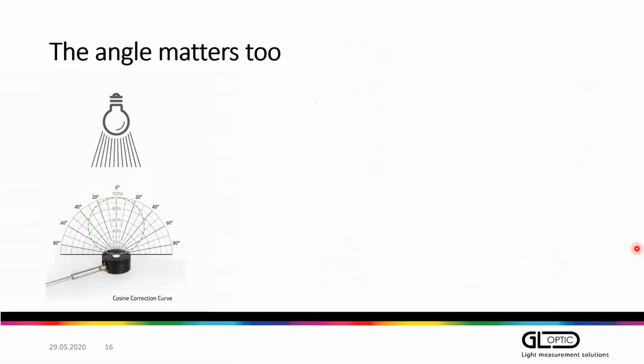What about the angles? The same thing. If you change the angle, then the amount of energy appearing on the surface will change. So this graph here shows the cosine correction curve for the irradiance probe. Because at the zero angle you have full signal level, let's say 100%.